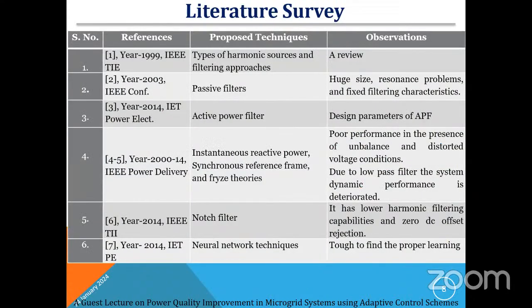If you see the literature survey, from 1999, in the IEEE Transactions on Industrial Electronics, they gave a brief review about what the harmonic sources are and what types of filtering techniques are available. In 2003, the authors proposed passive filters. In 2003 and before that, only passive filters were used for power quality improvement and harmonics reduction. But the drawbacks of passive filters are that they are huge in size, and by using them we can remove only particular selective harmonics, either one or two or three. For every individual harmonic, we have to design a separate passive filter. That is one of the major drawbacks of passive filters.